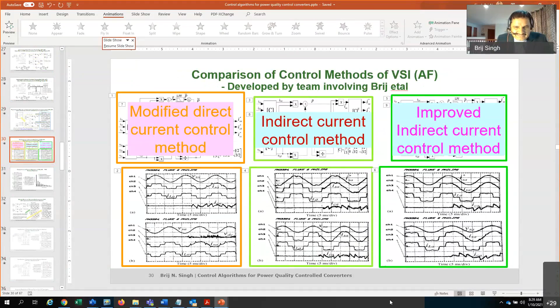If I'm seeing this correctly: the first one, black line, shows load current without any compensation. From your legend, that's 29.7% TDD. With the modified direct current control of the active filter, supply current reduced to 10.2% TDD - that's the second color, the light one. With the indirect current control, the next bar. Then the bar with no color is with the improved indirect control algorithm.